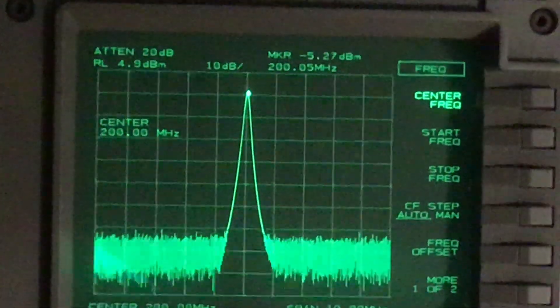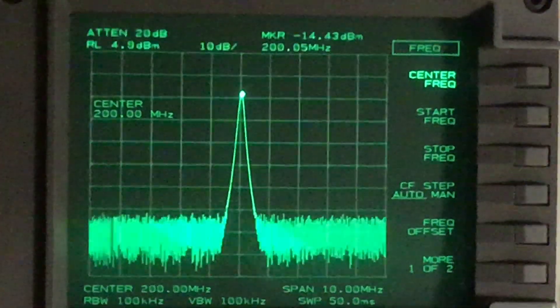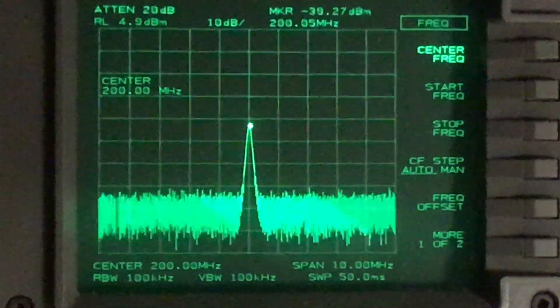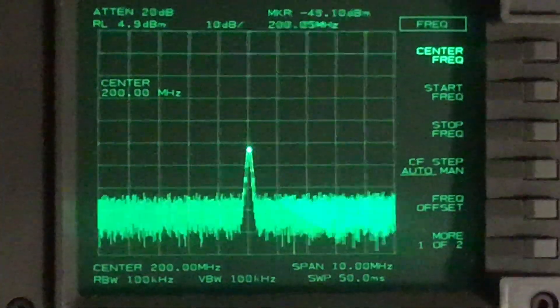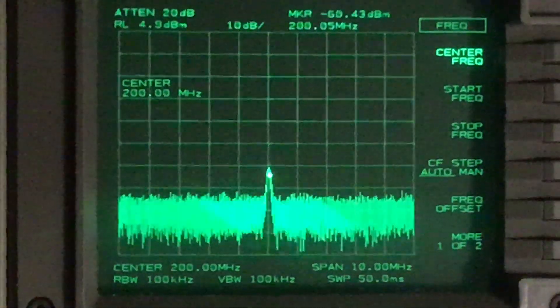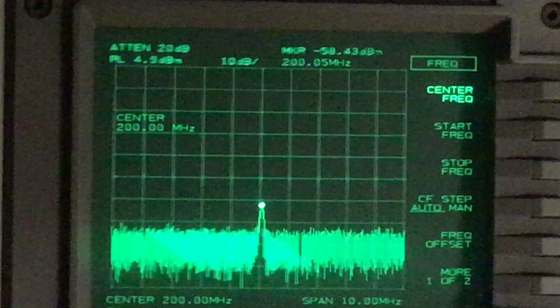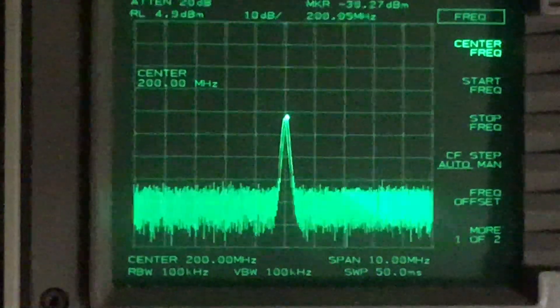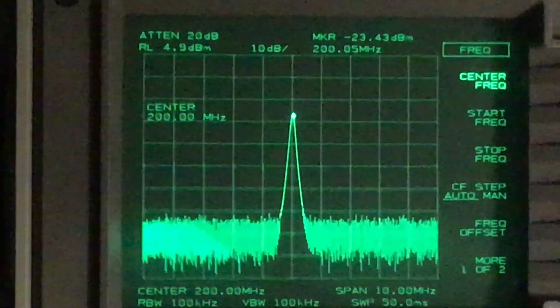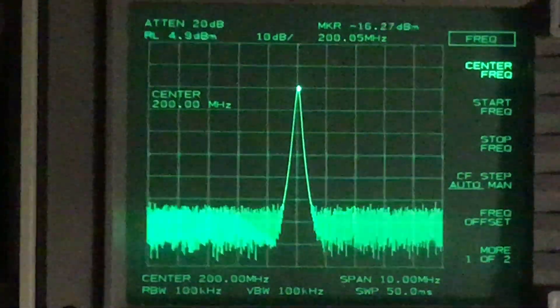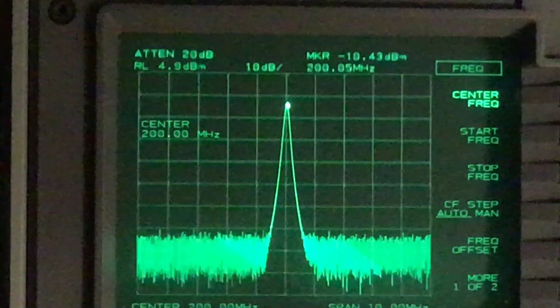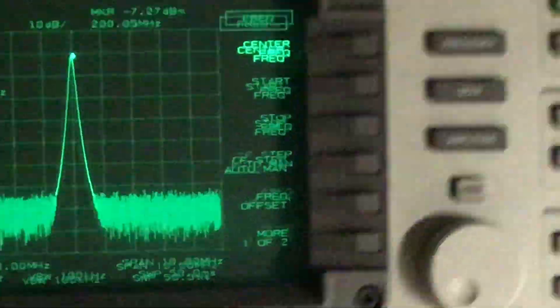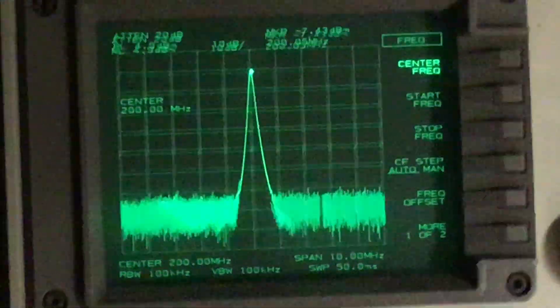You know, up and down and in between the RF attenuator clicks, it's not dropping the carrier, losing it. You do find that with some radio test sets, not necessarily Marconi ones, but other manufacturers, depending on how well the RF attenuator section is made with the relays.